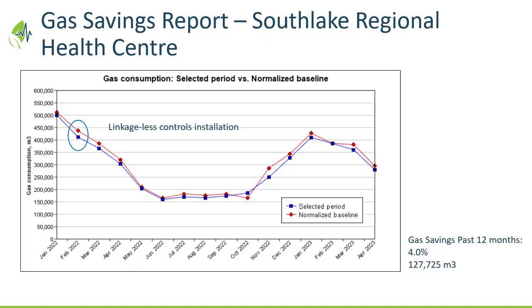Here's what we see when we track the savings. So again, we're looking at these numbers for every one of the member hospitals every month. And back in February of 2022, the hospital installed, with Thermogenics, linkageless controls on the boilers there, which Paul will explain when we get to that point as to how that improves the efficiency of the boiler plant. Just a single measure, and what we're going to be talking about today is what more could they have done and what more are they planning to do right now? What is that whole shopping list that's in the checklist that you have in front of you right now? But you see the red dots are the weather normalized baseline from the previous year.